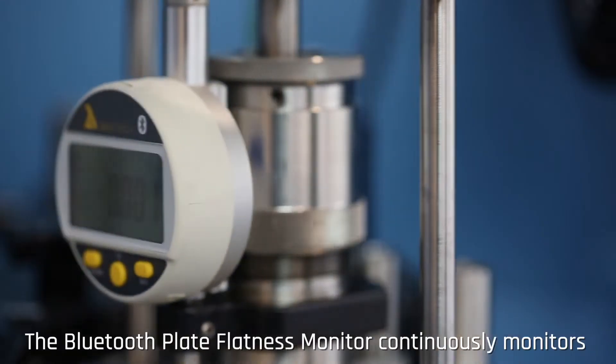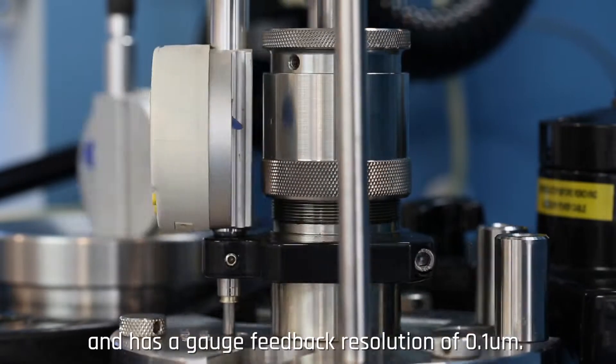The Bluetooth plate flatness monitor continuously monitors and controls the lapping plate flatness to within 0.5 micron of the target and has a gauge feedback resolution of 0.1 micron.